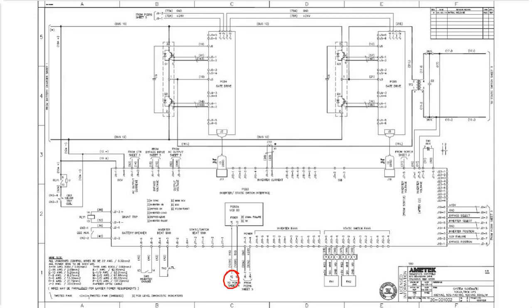Once again, here are our fiber optic cables. Here's where our fan sensing is connected. Our fans have tachometers in them. They are monitoring the speed of the fans, and if the bearings are starting to go, then the fan will slow down. This is what monitors the fan tachometer here. What else do we have on this board that's of interest to you? Nothing really. It just tells you what the LEDs on the board are. Okay.